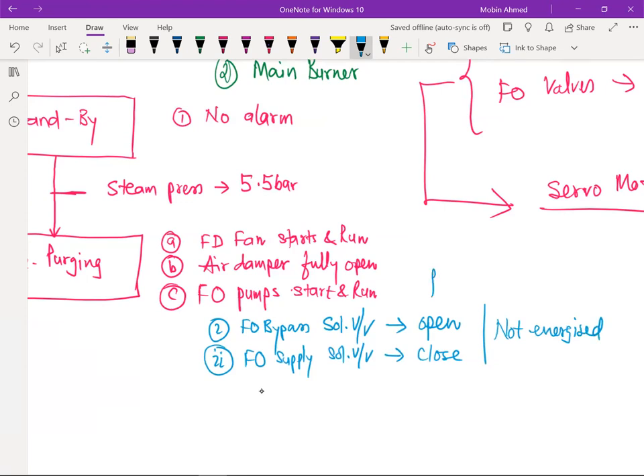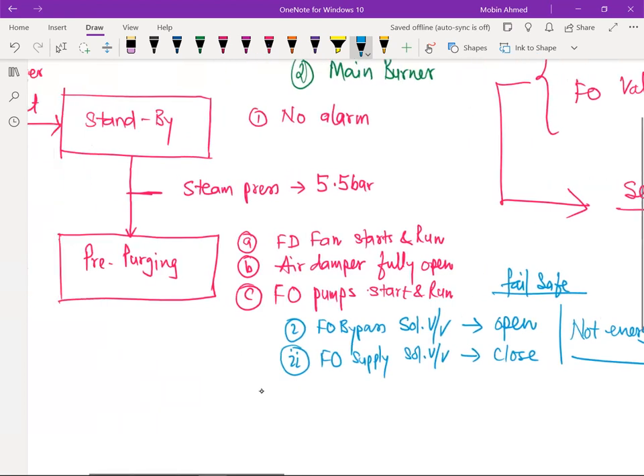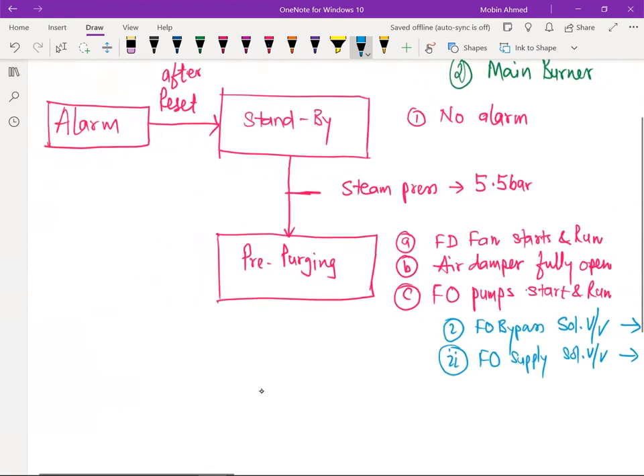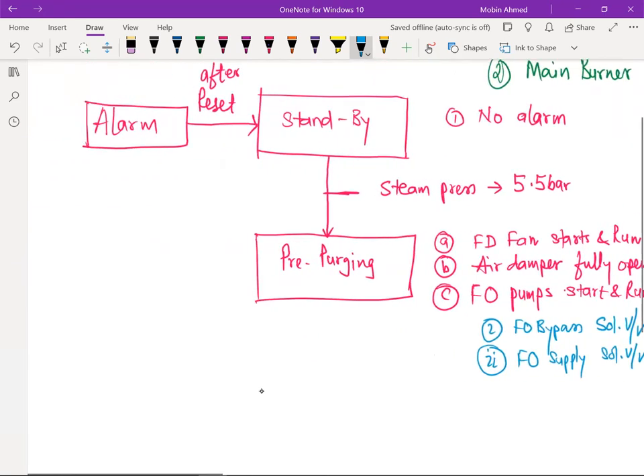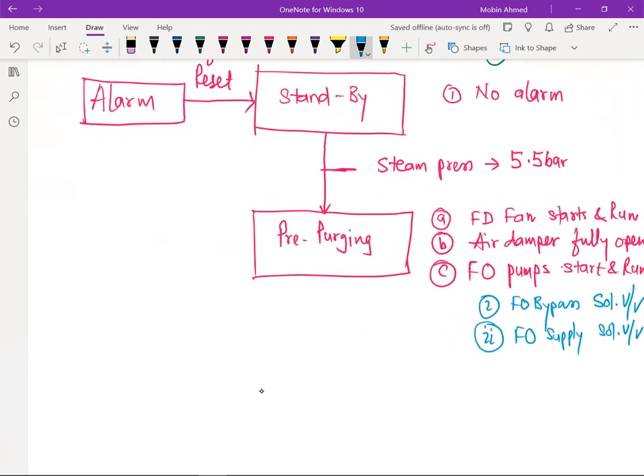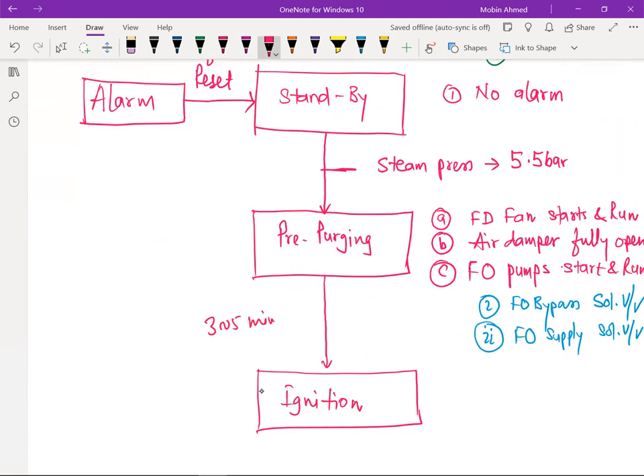This is known as fail-safe mode. In case the power goes off, it will go to fail-safe: the bypass will open and the supply will remain closed always. So this is the not-energized condition and this is the valve position. The bypass solenoid valve is always open, and the FO supply valve is always closed. Once the pre-purging time is over, whatever the time is, you can see it in your manual. Generally it is 3 to 5 minutes, and it varies depending on the make and model. Then it goes to the ignition.